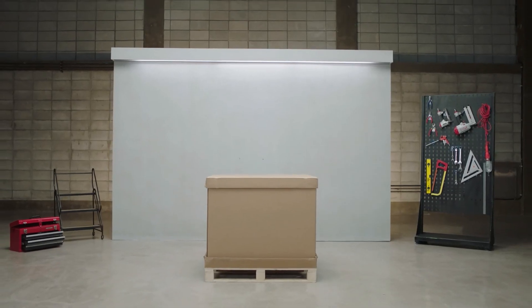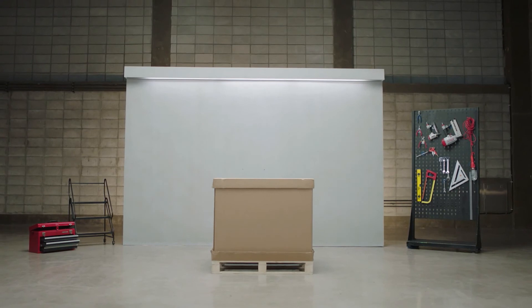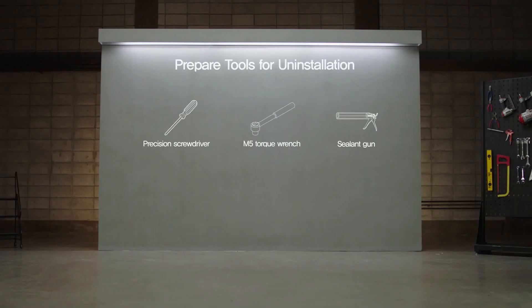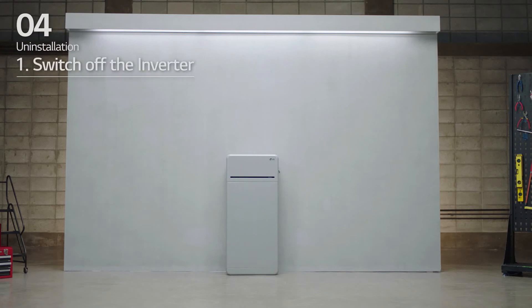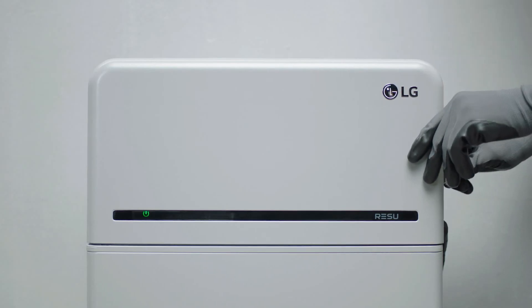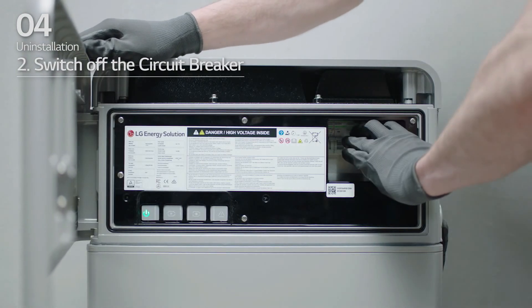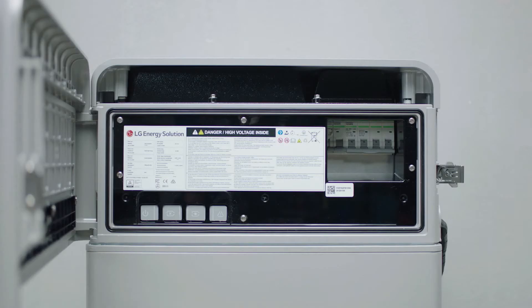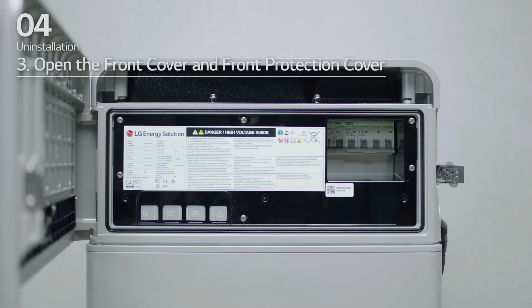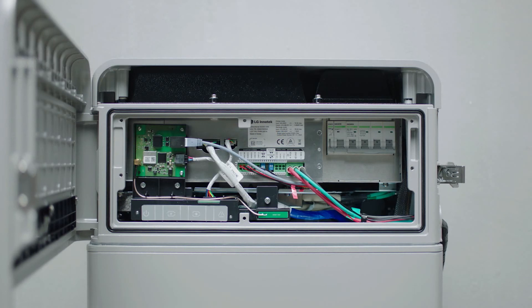LG Energy Solution will now show you how to uninstall the RESU16H Prime. Prepare tools for uninstallation. One, switch the inverter off. Two, open the front cover and switch the circuit breaker off. Make sure it is in the off position. Three, loosen the six bolts and remove the front protection cover.